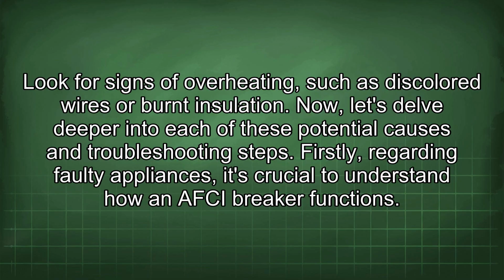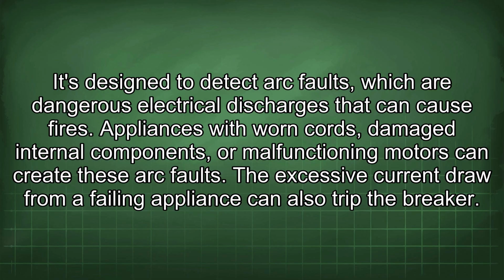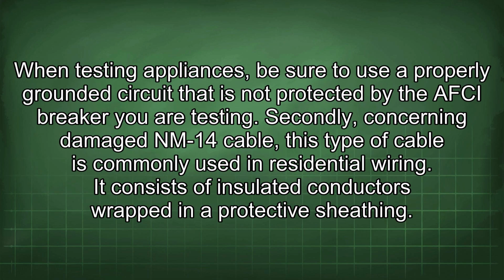Now let's delve deeper into each of these potential causes and troubleshooting steps. Firstly, regarding faulty appliances, it's crucial to understand how an AFCI breaker functions. It's designed to detect arc faults, which are dangerous electrical discharges that can cause fires. Appliances with worn cords, damaged internal components, or malfunctioning motors can create these arc faults. Excessive current draw from a failing appliance can also trip the breaker. When testing appliances, be sure to use a properly grounded circuit that is not protected by the AFCI breaker you are testing.